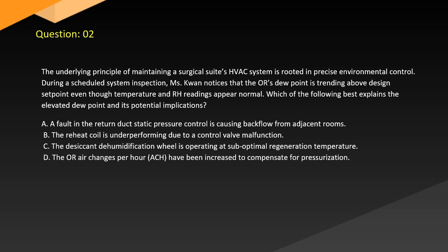Question 2. The underlying principle of maintaining a surgical suite's HVAC system is rooted in precise environmental control. During a scheduled system inspection, an technician notices that the dew point is trending above the design set point, even though temperature and RH readings appear normal. Which of the following best explains the elevated dew point and its potential implications?